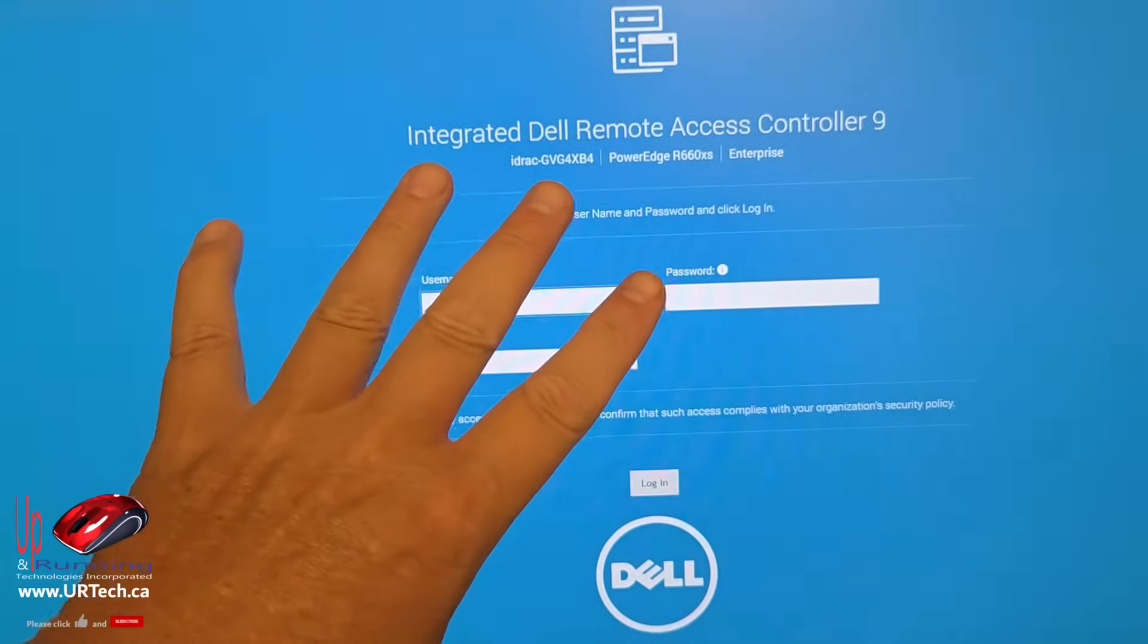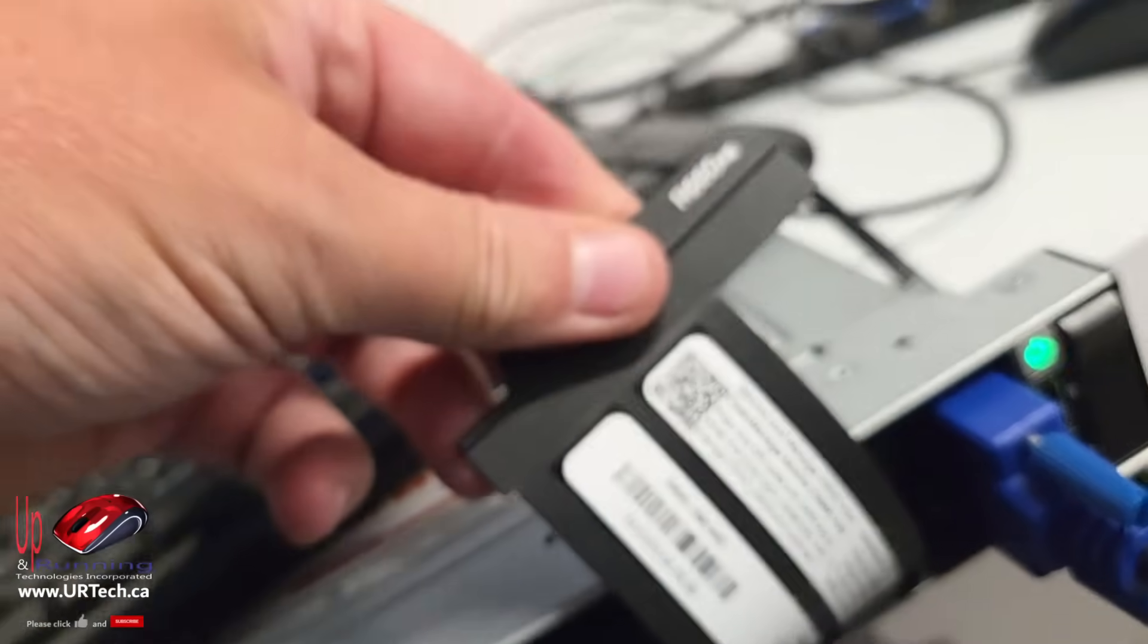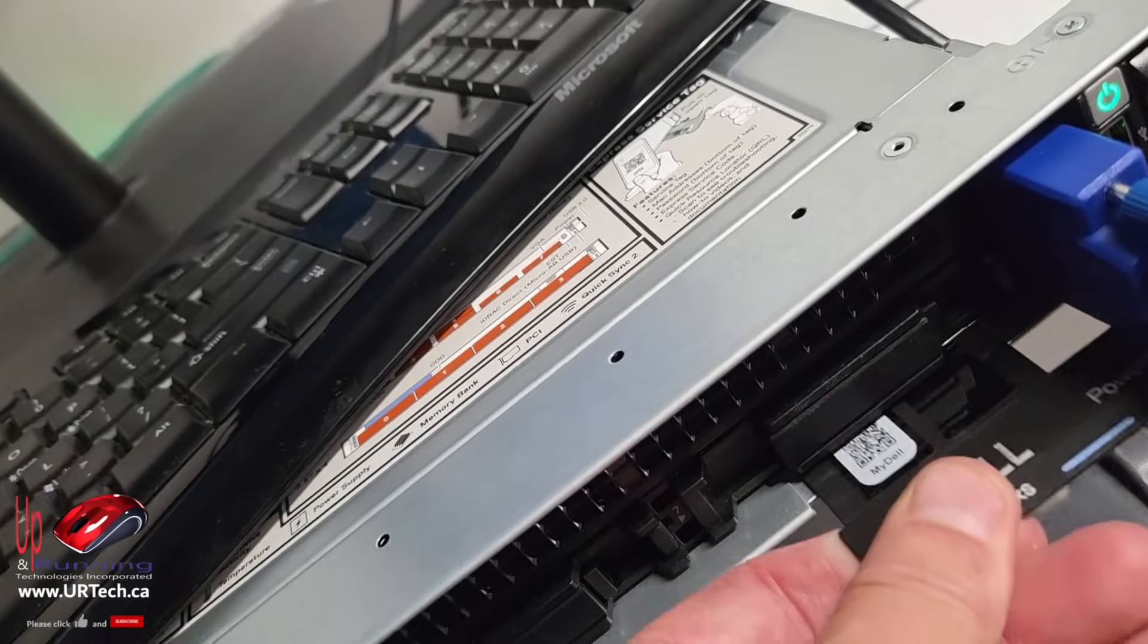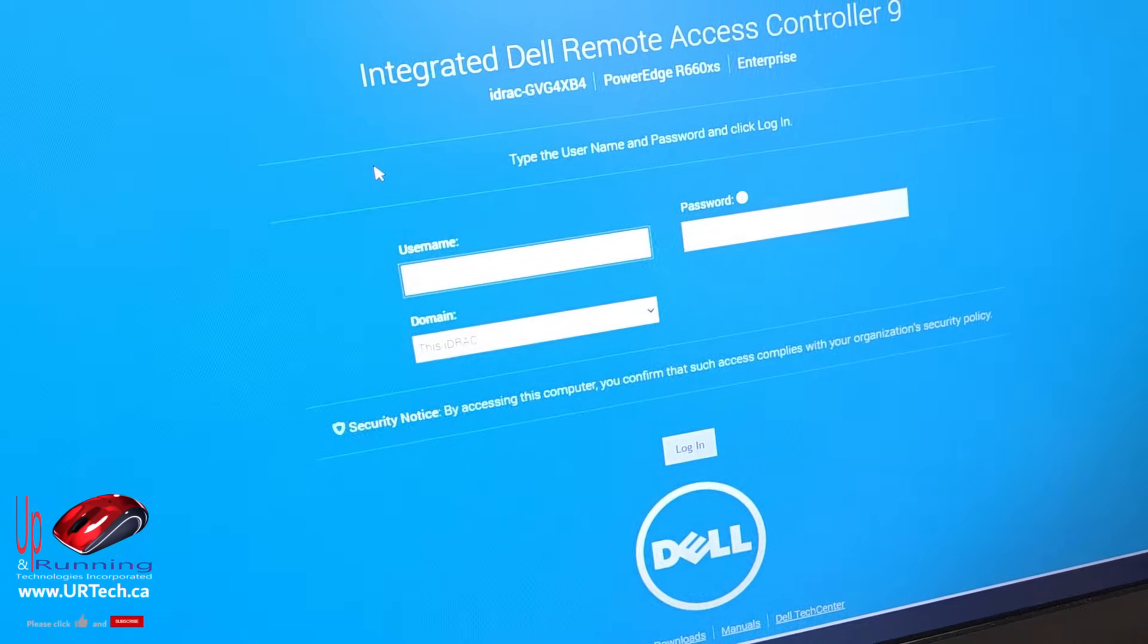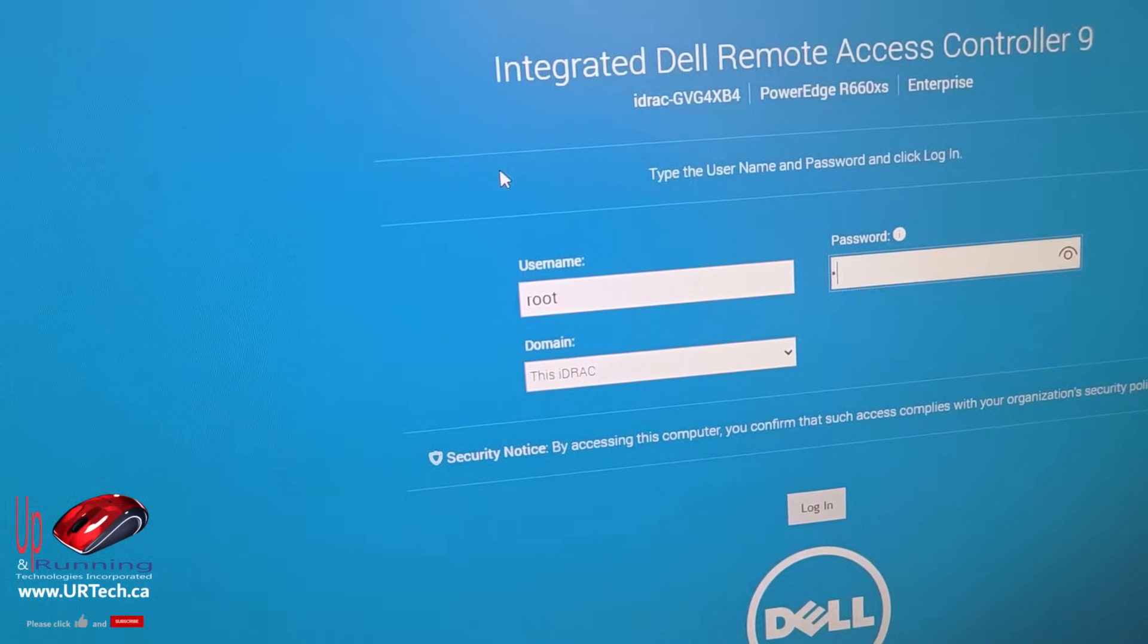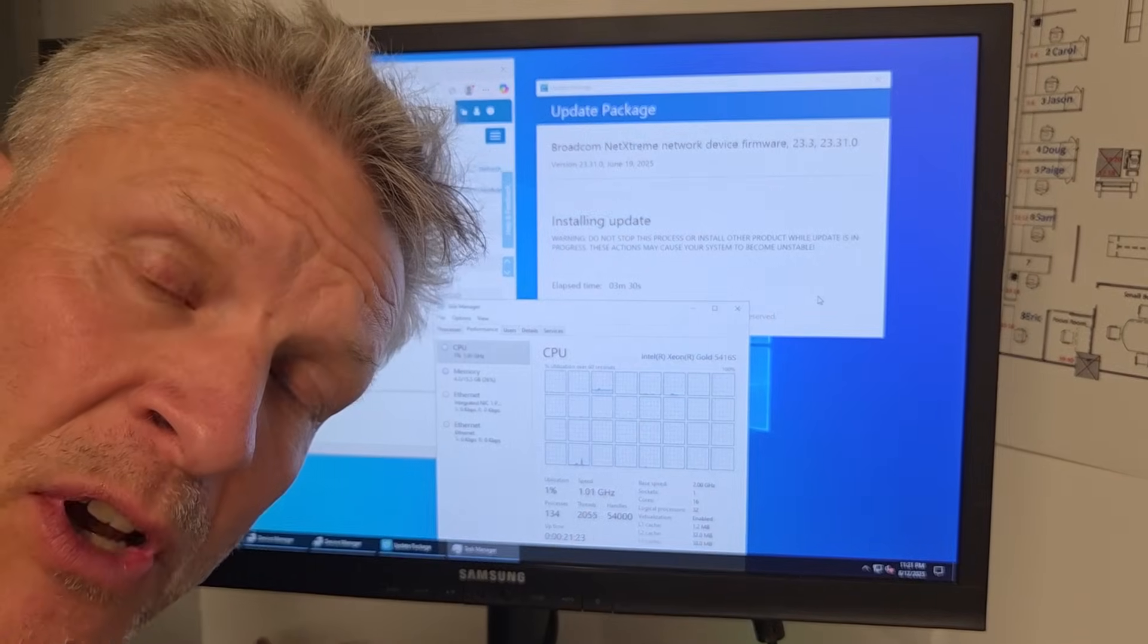Now you think you're stuck. You don't have username and password. Well, the default is root, username, and the password is Calvin. C-A-L-V-I-N. However, in some systems, they actually put codes right here. Back of the pullout card. However, I'm pretty sure ours is root and Calvin. Yup, bingo.